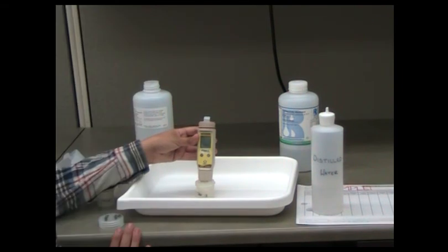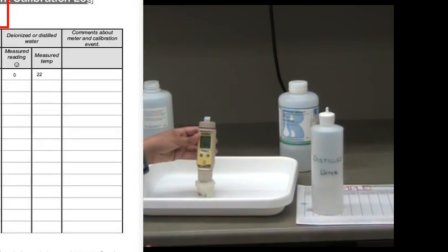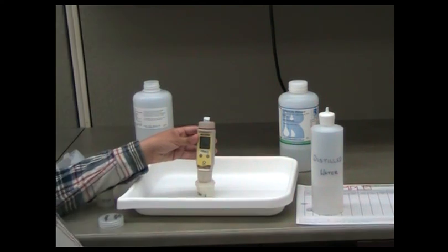This value ought to be zero. If tap water or spring water is used for this step, the reading on the meter will not be zero. Record the temperature displayed on the screen. You have now completed the calibration process for the EC tester.